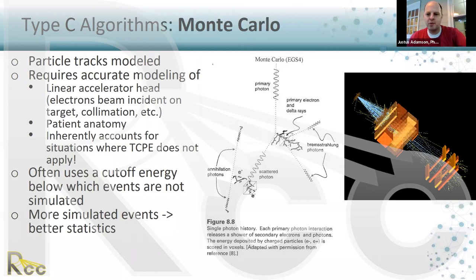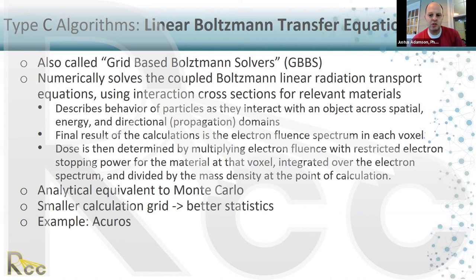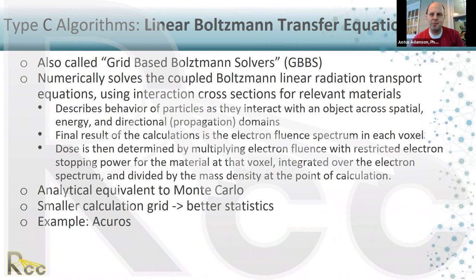Grid-based Boltzmann solvers (GBBS), also called linear Boltzmann transport equation solvers, numerically solve the coupled Boltzmann radiation transport equations using interaction cross sections for relevant materials. They describe particle behavior as particles interact with an object across spatial, energy, and directional domains. The final result is the electron fluence spectrum in each voxel; dose is then determined by multiplying the electron fluence by the restricted electron stopping power of the material at that voxel, integrated over the electron spectrum. Better statistics are achieved with a smaller calculation grid rather than more particle histories. The main example of this algorithm type is Acuros.